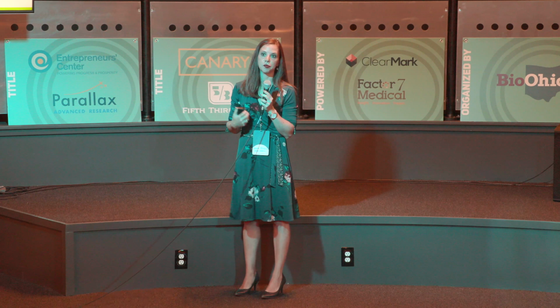So, whether your device is provided single-use sterile, or whether your device is an instrument that goes through repeated cleaning and sterilization, it's really important that you go through the validation process of ensuring that your worst-case scenario device is able to be sterilized appropriately based on parameters that are required. There's a host of standards for both cleaning as well as the sterilization and packaging and distribution and shelf life. So, just placing your device in a bag and shipping it to a hospital, there's an entire protocol of requirements and 6 to 8 weeks of testing that you must undergo to ensure that there's no puncturing of the device during transport, that you're not compromising any sterility throughout that process, and ensuring that the device, as it leaves for the end user, arrives in the same manner.